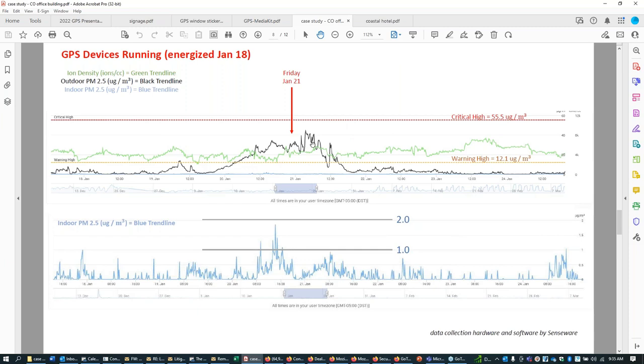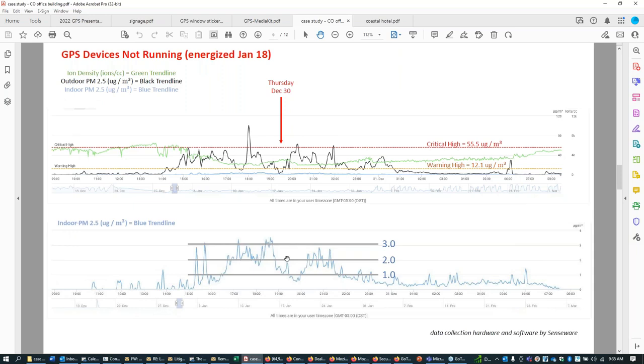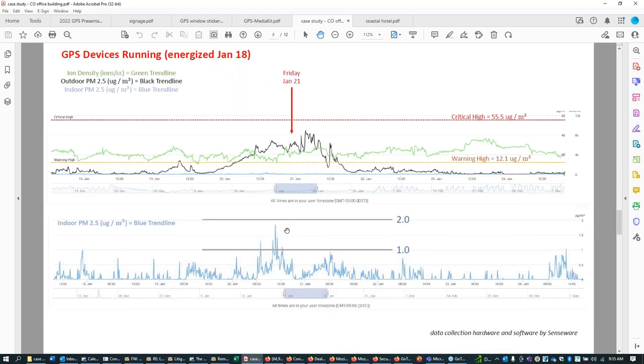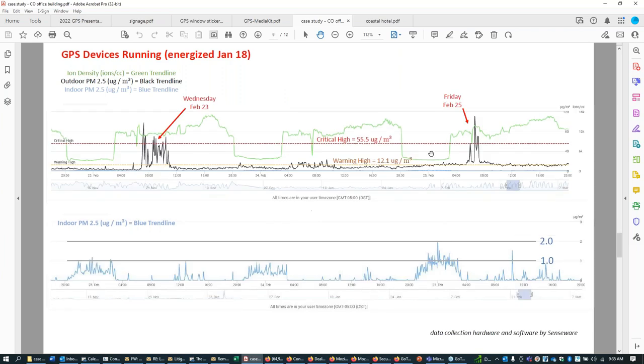What we showed, though, was that after the devices had been turned on for 3 days in this case, and then for a couple of weeks on the later events, look at the difference with indoor air quality. The indoor PM 2.5 curve, whereas here it stayed below 3, during this event it stayed below 2. And during these two events, the indoor PM 2.5 stayed below 1 microgram per cubic meter. So this was a really impressive before and after data collection exercise that is very hard to obtain, because when you've got an office building that is not fully occupied, that is doing a lot of ventilation, it's sometimes hard to see the before and the after. But this was a really nice case study that we were able to capture at this office building in Denver.